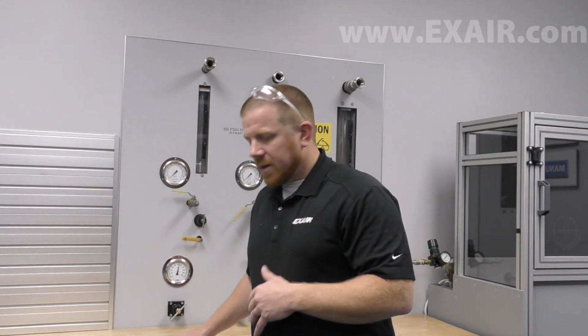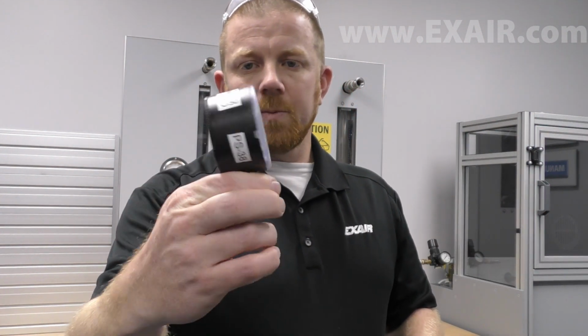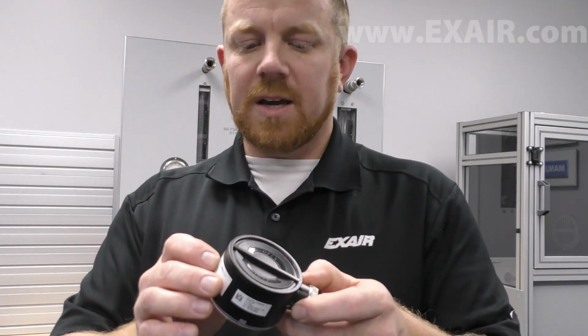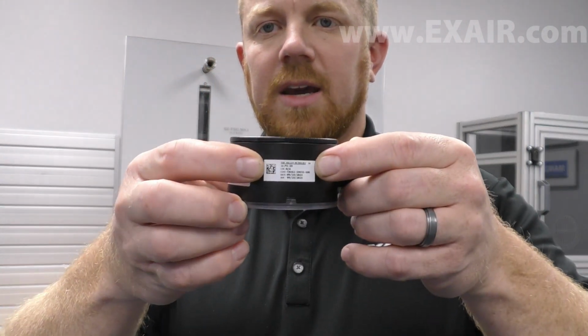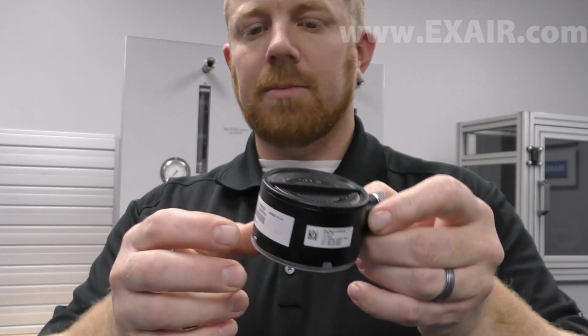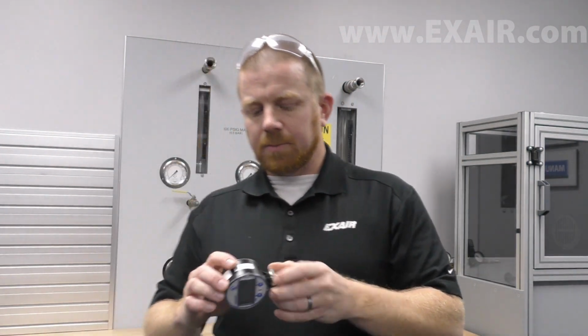We will often, at that point, use a digital pressure gauge. This is one that we have on hand here. It actually operates off of a pressure transducer inside of the housing and some circuitry. These can be calibrated. Once calibrated, any gauge will generally have a certificate of calibration with it, some kind of indicator giving a date, and just some traceability to go with it.